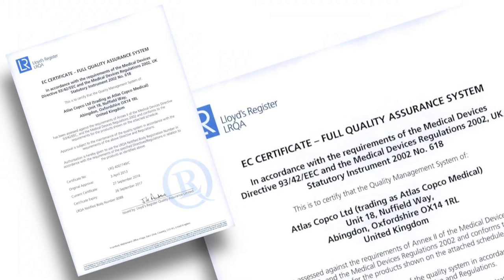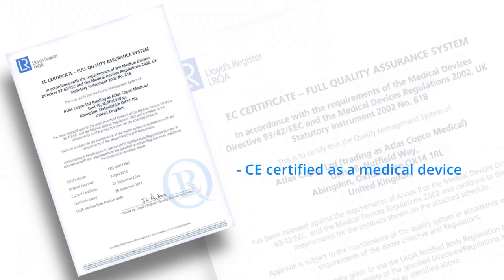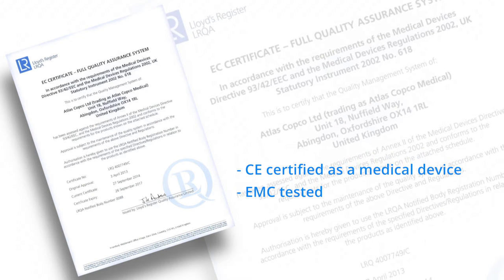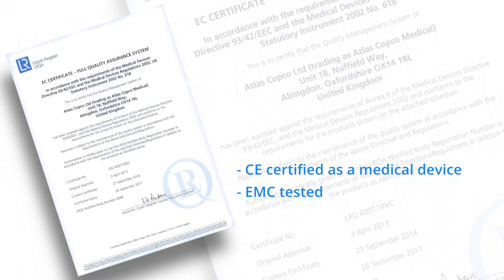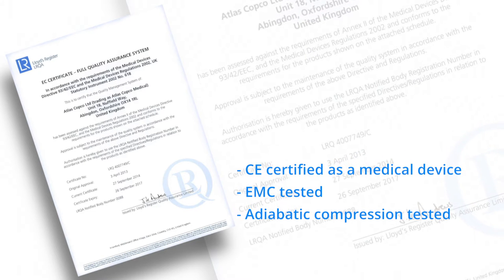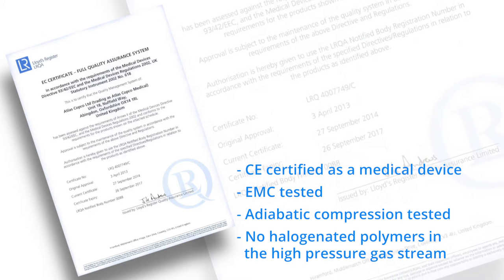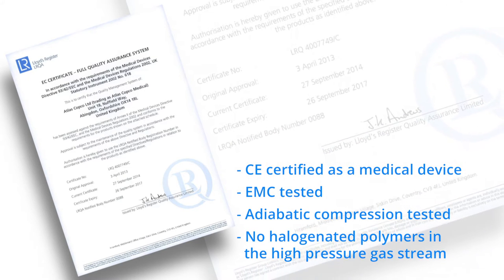Our new manifold is certified, offering you complete peace of mind. The LifeLine MCS is CE marked as a medical device. As such, additional rigorous testing is required for EMC compatibility, ensuring the system is not affected by electromagnetic interference once on site. Our medical grade regulators are fully certified for adiabatic compression testing, protecting against shock loading, as well as using halogen-free polymers, removing the risk of highly toxic chemicals passing into the pipeline in the unlikely event of combustion.